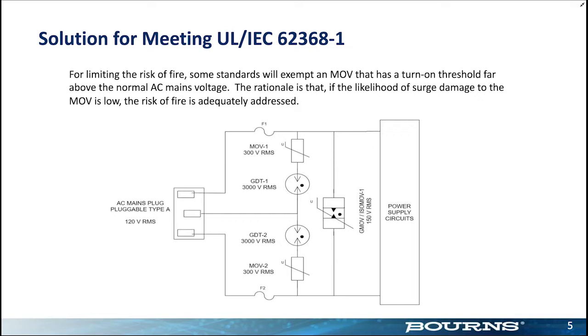The typical failure mechanism for an MOV is leakage over time. If there's always a voltage across the MOV, either DC or AC, the leakage current goes up over time. I'm talking years. And leakage current goes up, there's a voltage across it, that's power dissipation, which makes it get hot, which makes leakage go up even more, which makes it get even hotter. So, right, you got this thermal runaway mode.